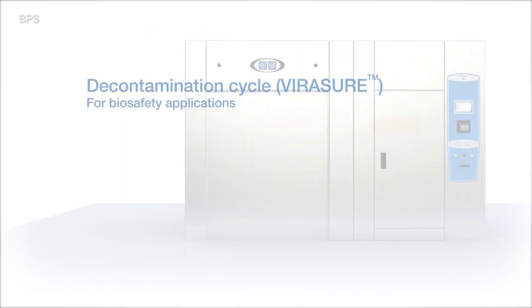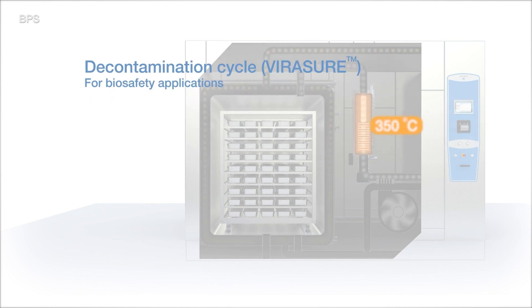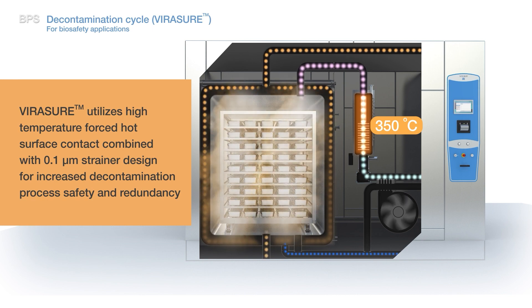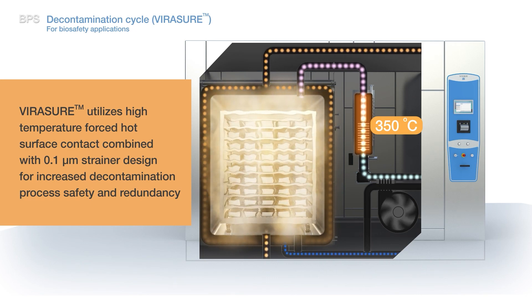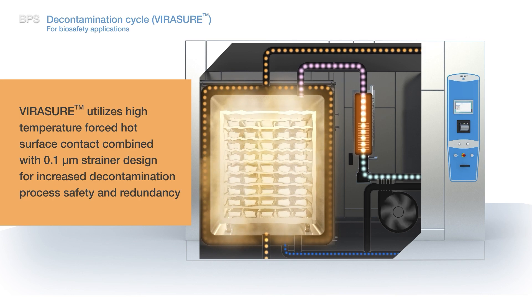The VIRASURE air decontamination system is used for safe conditioning of the chamber prior to decontamination exposure, resulting in improved redundancy and safety for the most demanding biosafety decontamination applications. VIRASURE combines forced high-temperature surface contact decontamination with 0.1 micrometer filtering, provided by a permanently installed, maintenance-free stainless steel strainer and electrical heater element tightly welded inside a housing. This feature protects facility personnel and the environment, preventing any possibility of contamination when handling biohazardous materials in a decontamination sterilizer.